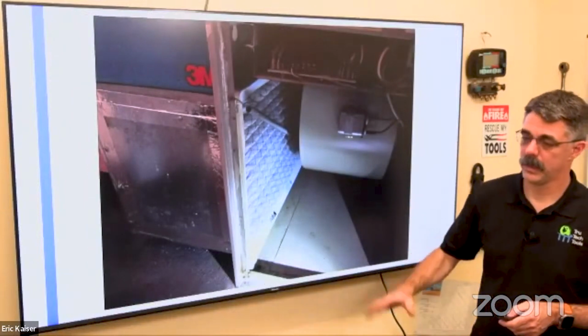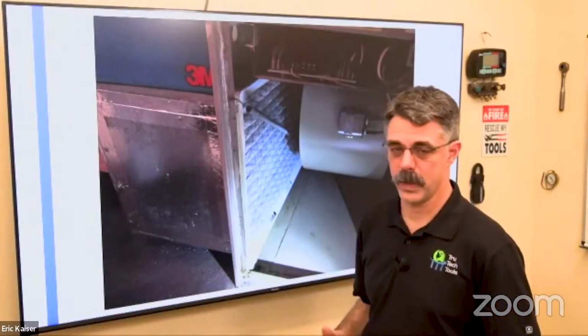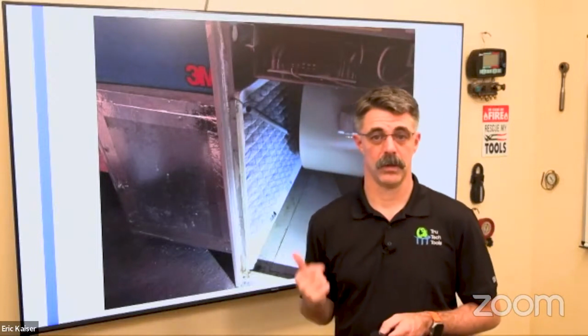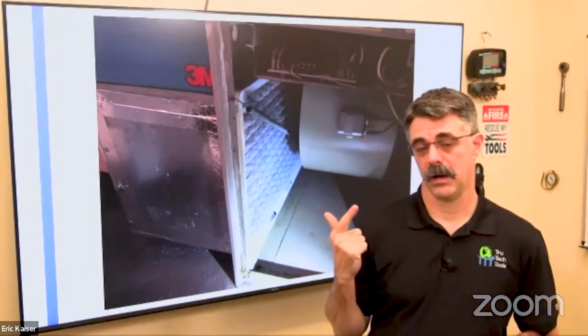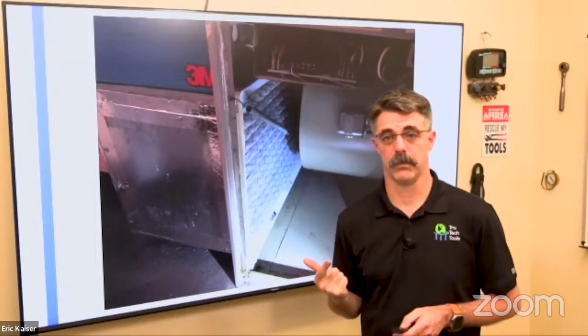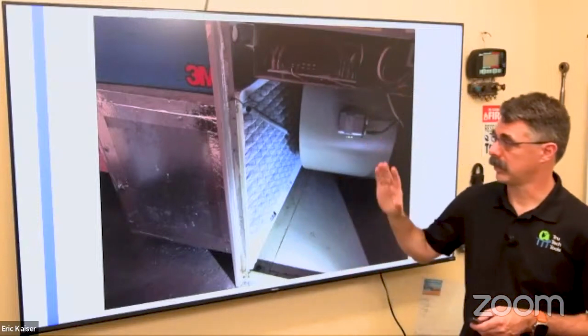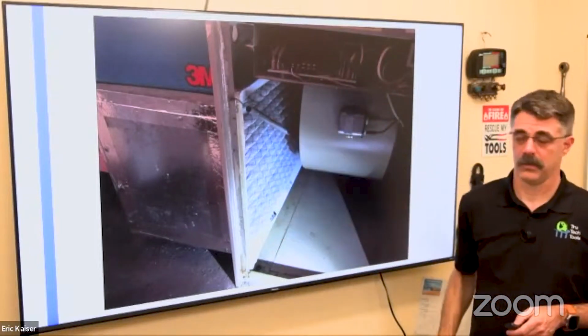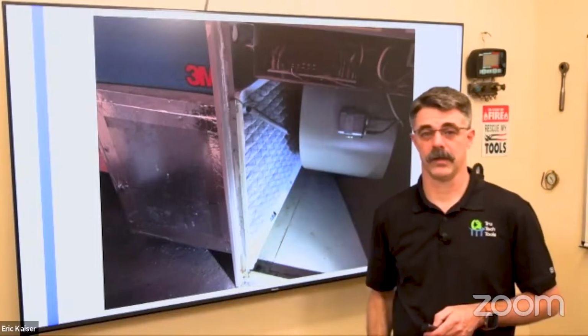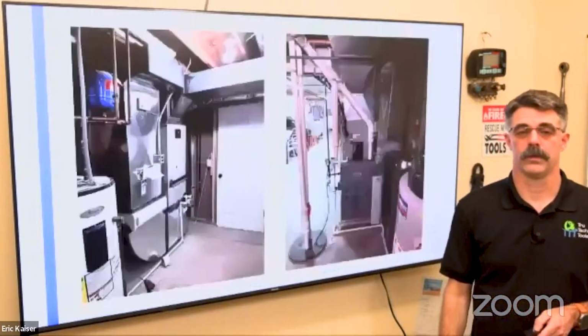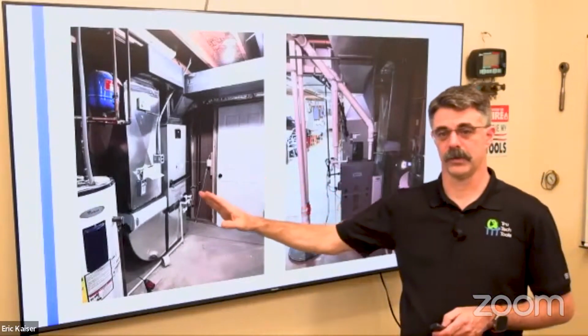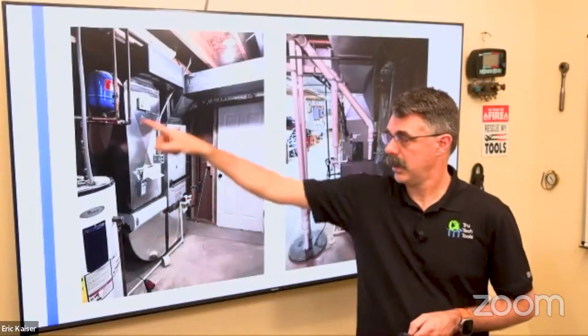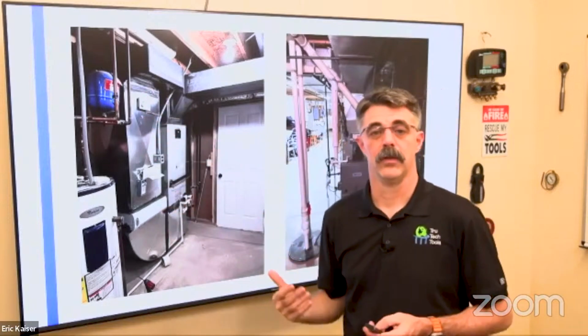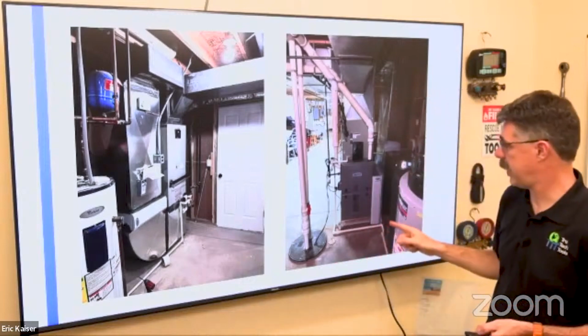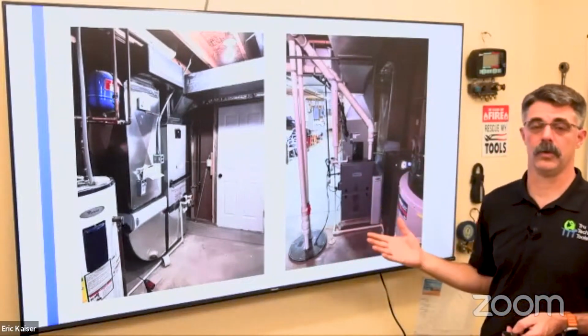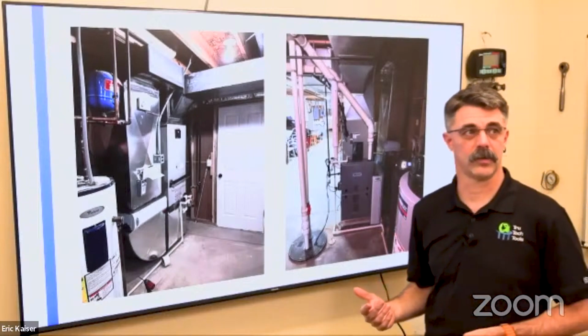Right? When we're putting in new equipment, one of the biggest things we can do to improve the system, so it improves the dirt catching capacity, and lower static pressure, which is great for motors, great for efficiency, great for noise, is to replace our 1-inch filters. Sometimes they're inside of a furnace, things like that. Get that 1-inch filter out of the system and go with larger size filters. Go with something bigger, go with bigger drops that are close to the equipment. There's really low hanging fruit to put in things like this when we're in there doing something, because it helps the longevity of the system and really improves things.